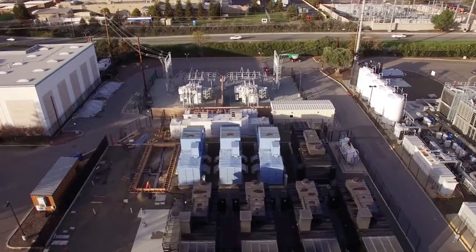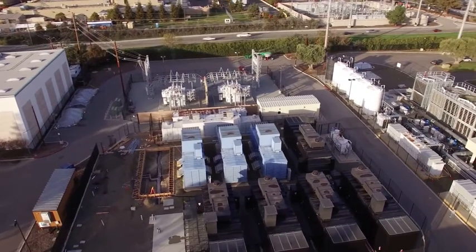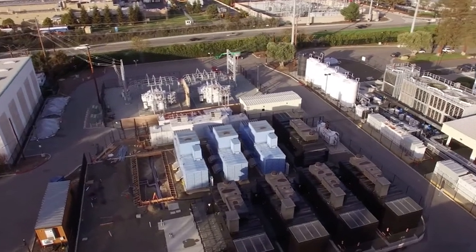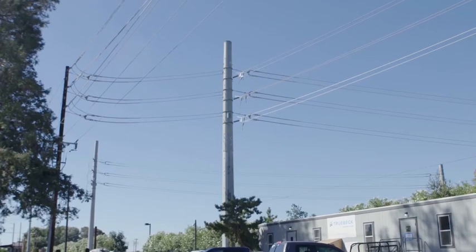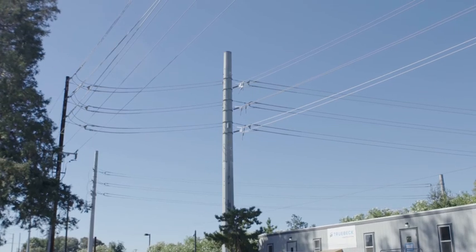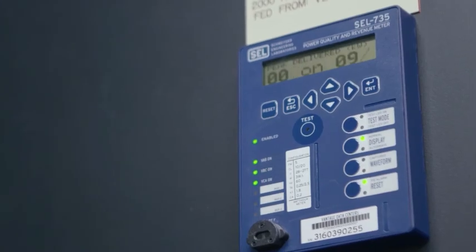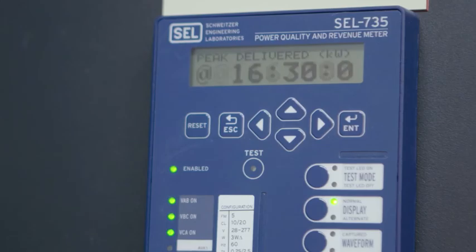Providing clean power is also very important, and something we found with our customers is that they're actually specifying that we measure and maintain very clean electrical power coming to them. The best way to do that is right at the meter, at the same revenue meter. That's really how we use the SEL 735 meter, to capture that revenue grade metering requirement, but also the power quality, harmonics, power factor, and anything related to ensuring clean, reliable power to the customer.